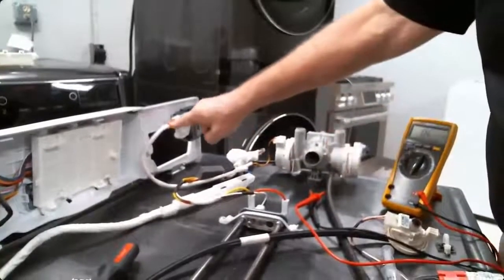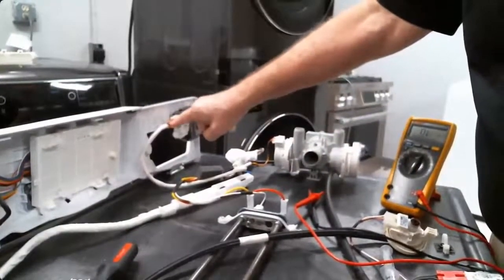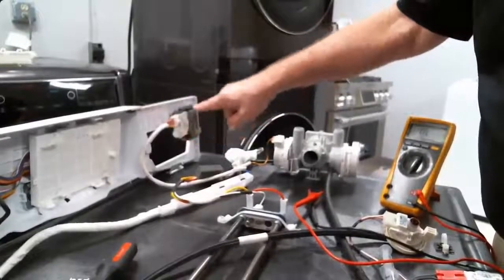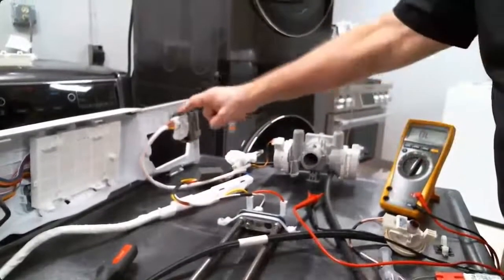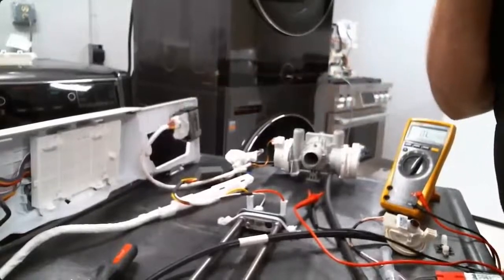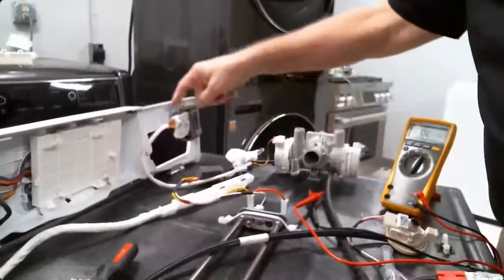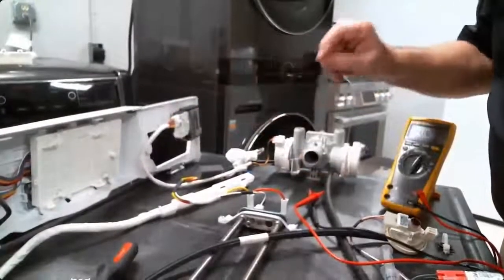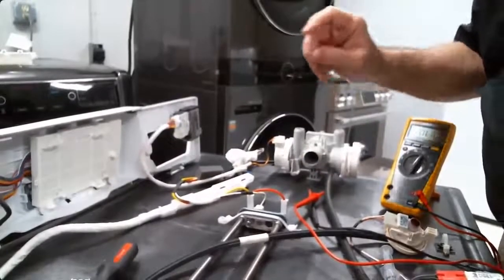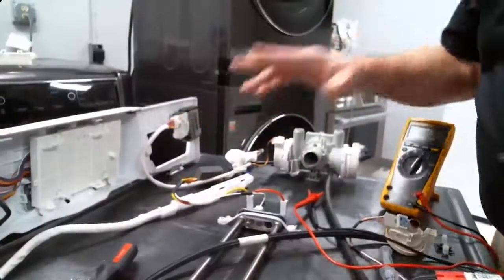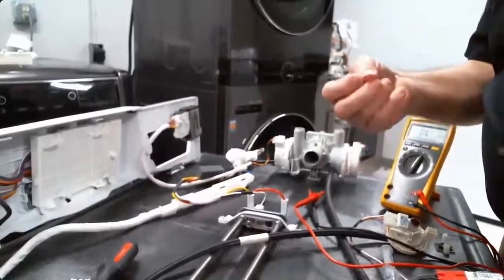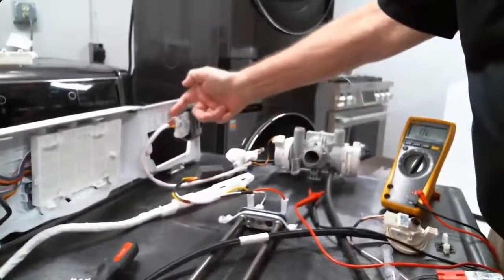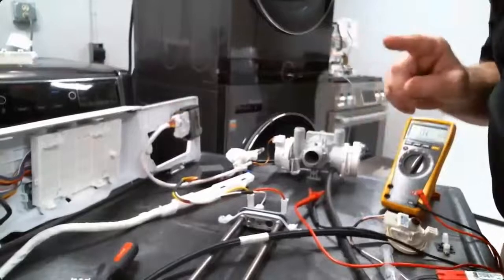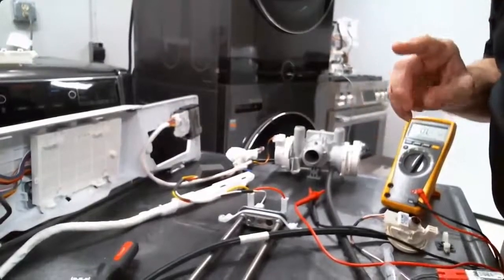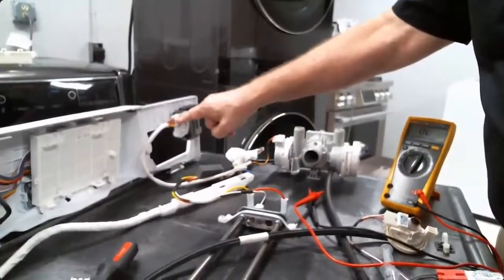You guys probably heard that. Through this same 110 circuit that we're heating up the PTC relays, we are going to energize a solenoid inside here. The difference on that solenoid, and that's why even though we have 110 volts there all the time we don't energize the solenoid, is that it's two things. It's voltage dependent, which means it uses 110 volts, but it's also frequency dependent. It isn't 60 hertz that energizes that solenoid.